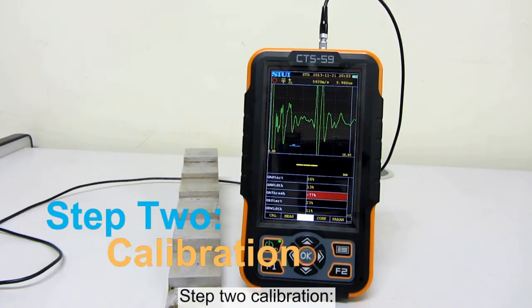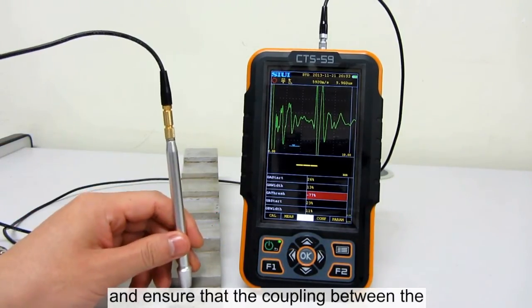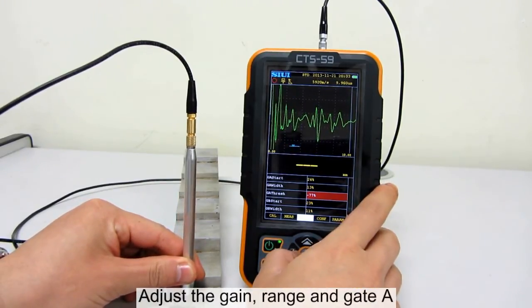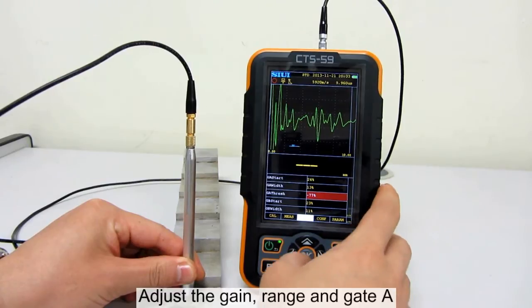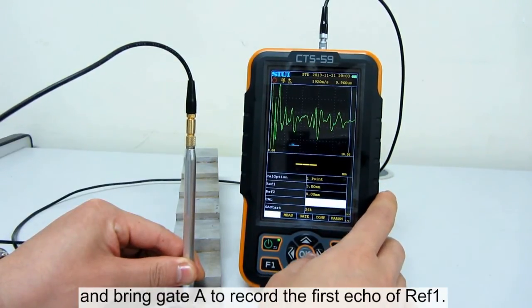Step 2: Calibration. Place the probe on the test block. Ensure that the coupling between the probe and the test block is good. Adjust the gain, range and gate A and bring gate A to record the first echo of reference point 1.